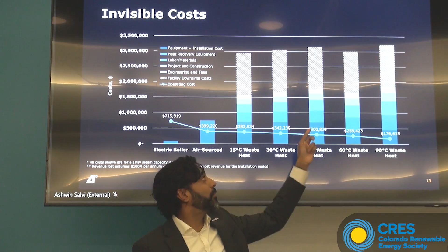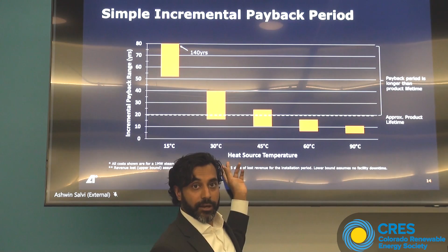Let me show you this in a different way. If I show you the rate of return - meaning how long it will take you to pay back the additional capital for a waste heat driven system as a function of temperature, compared to just an air source system. These systems are more efficient than the air source, but they cost more to deploy. We're talking about 140 years on the high side for 15 Celsius, which is the most common source of waste heat.